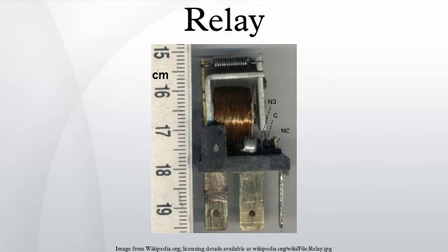Dry contacts: when switching very low level signals. Special contact materials may be needed such as gold-plated contacts. Contact protection: suppress arcing in very inductive circuits. Coil protection: suppress the surge voltage produced when switching the coil current.